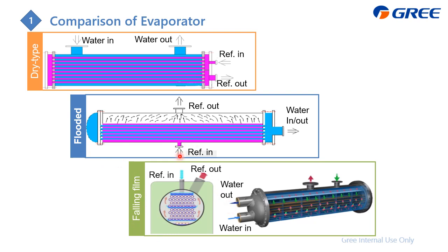And on the other hand, from the refrigerant inlet direction, you can also tell. Just compare the flooded type and the falling film type. The refrigerant only flows in at the bottom, and that's why it accumulates in this area. Then it will become gas. The refrigerant will flow out into the compressor. And for the falling film, the refrigerant comes in at the upside. It will flow in and spread onto the copper tube. Then it will become gas and flow out only from the upside. And also actually the dry type is obsolete, and the reason is the heat transfer efficiency is not that high.